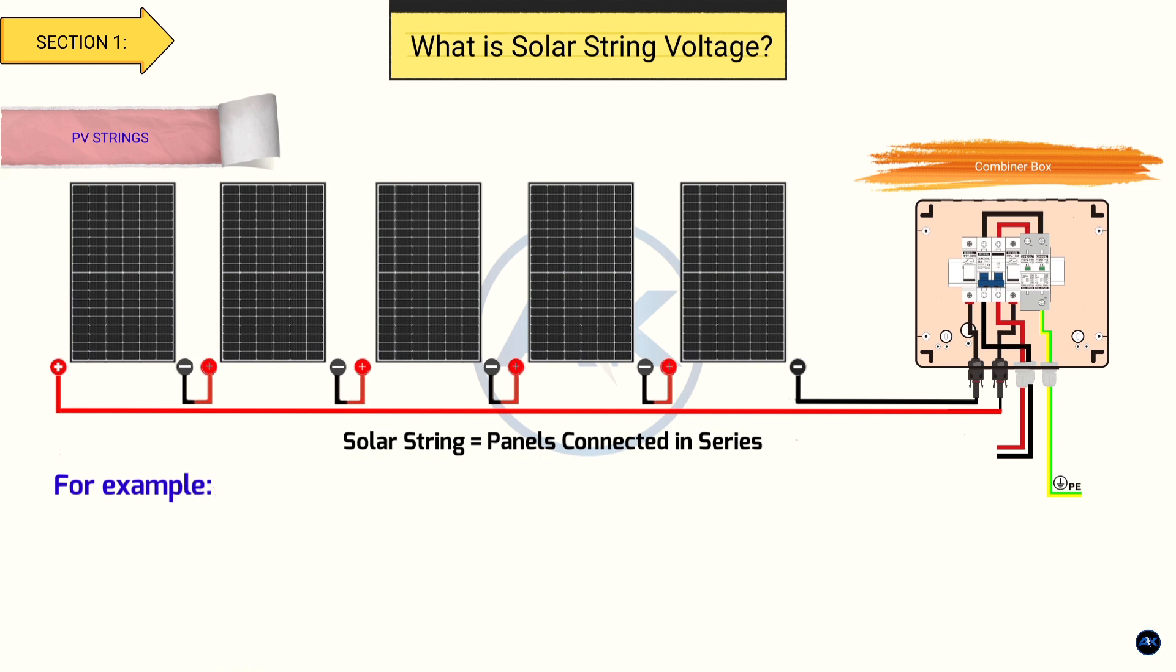For example, if you have 5 panels, each with an open circuit voltage of 40 volts, the total string voltage would be 200 volts. Simple, right? But here's the catch, every solar inverter has a maximum input voltage limit. Exceeding that limit can damage your inverter or even void your warranty.